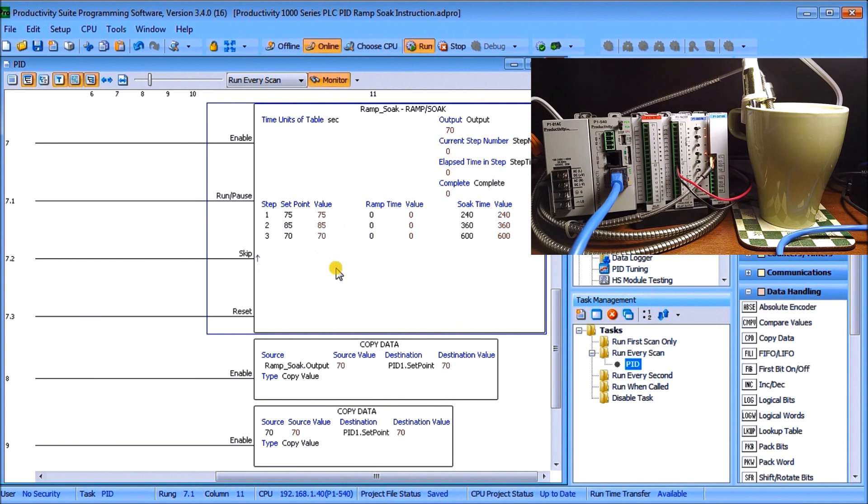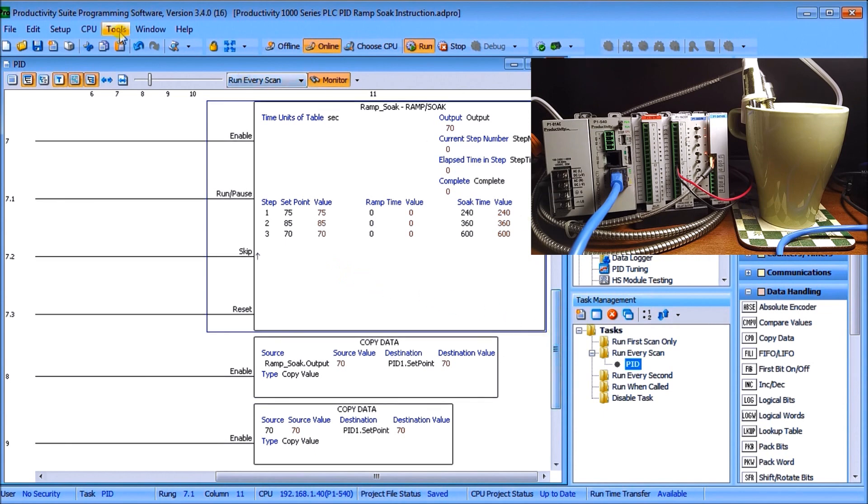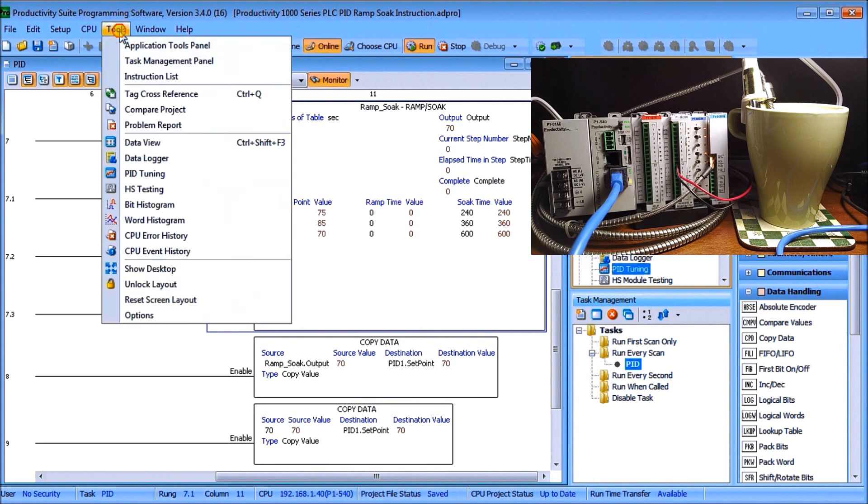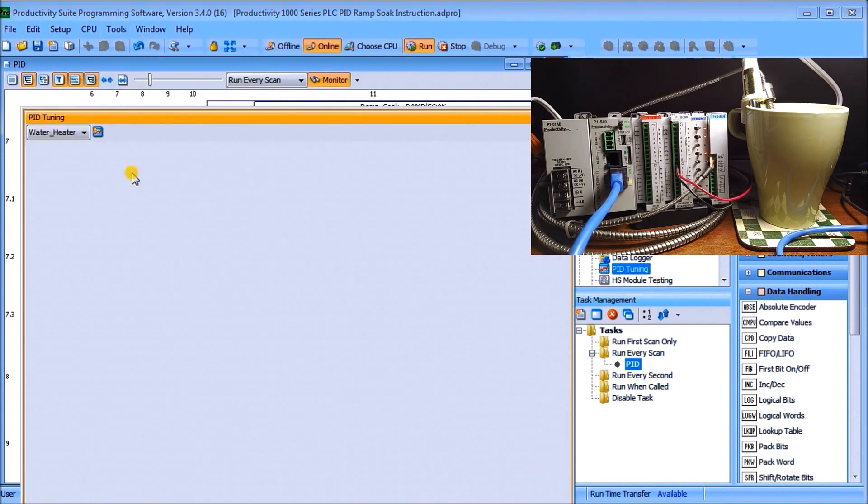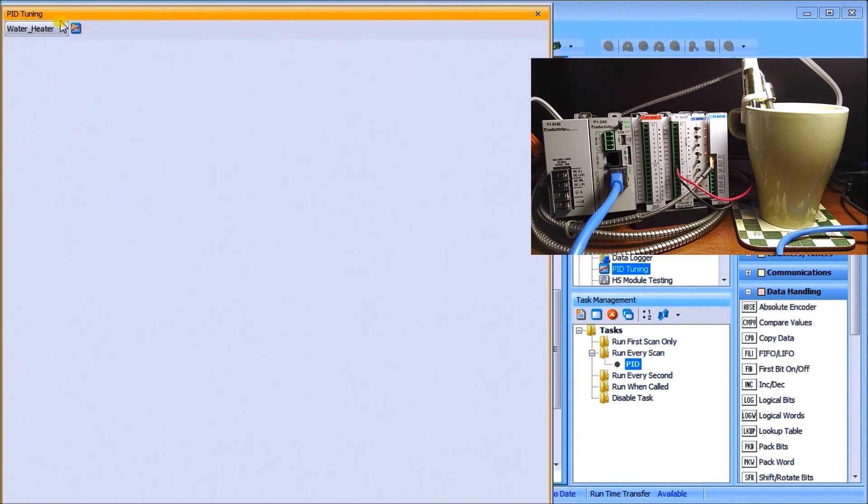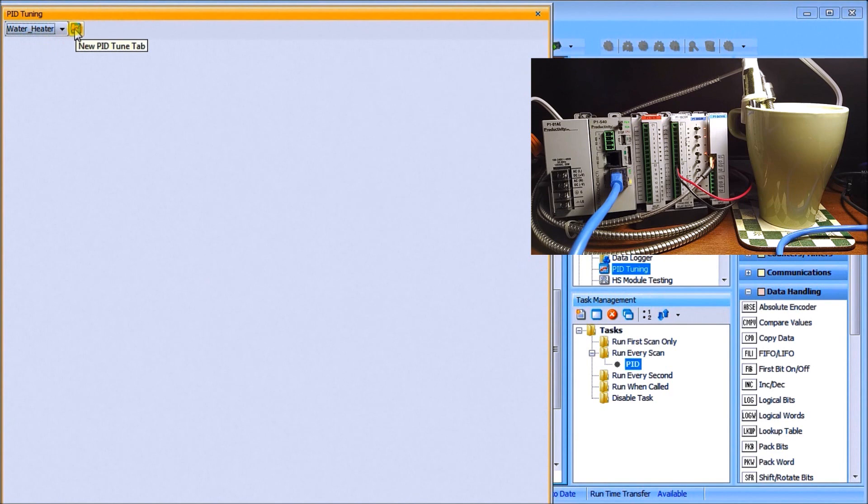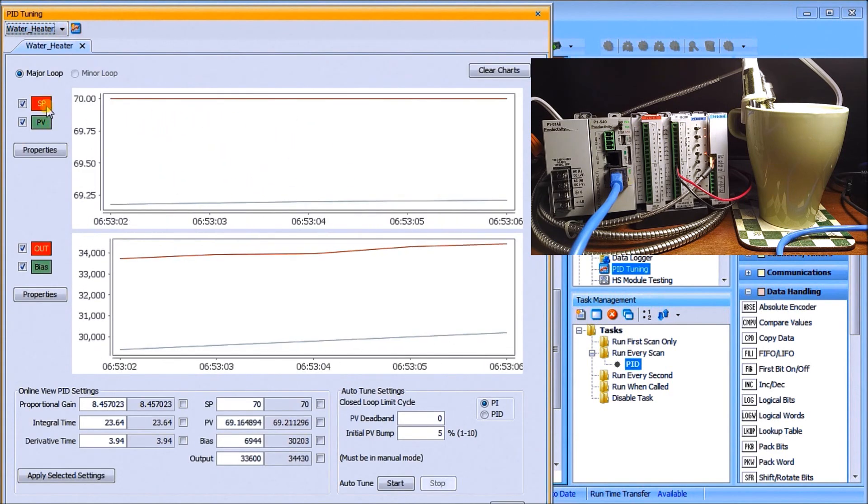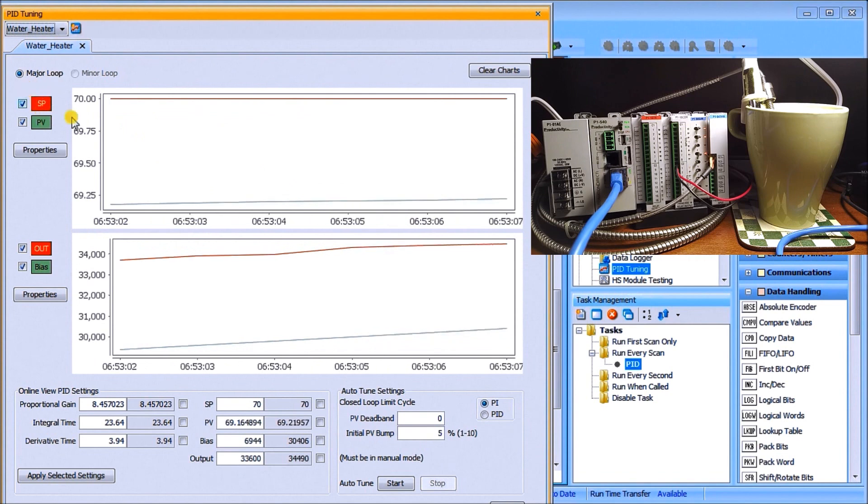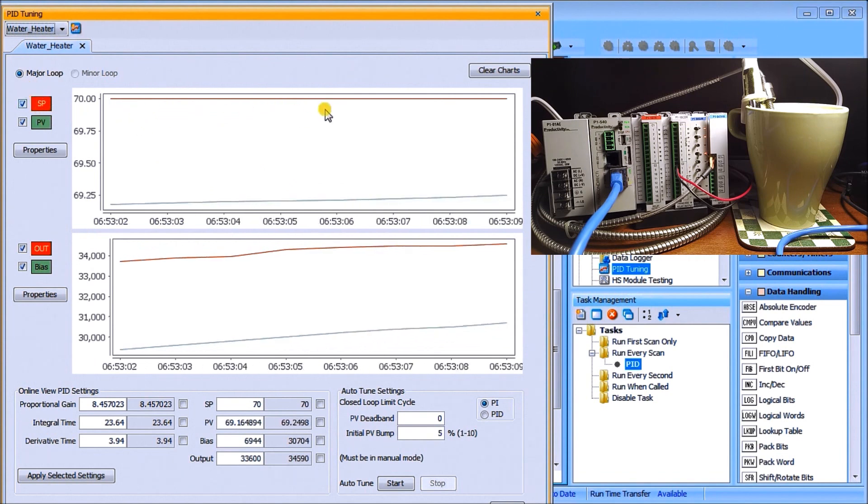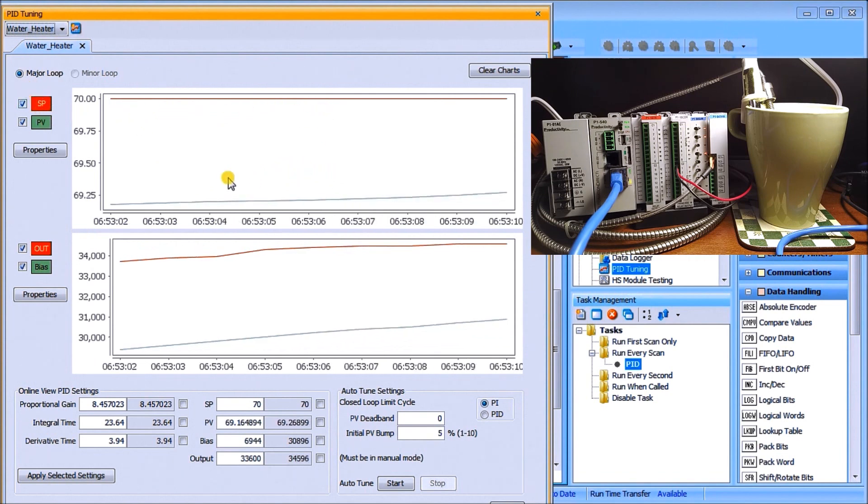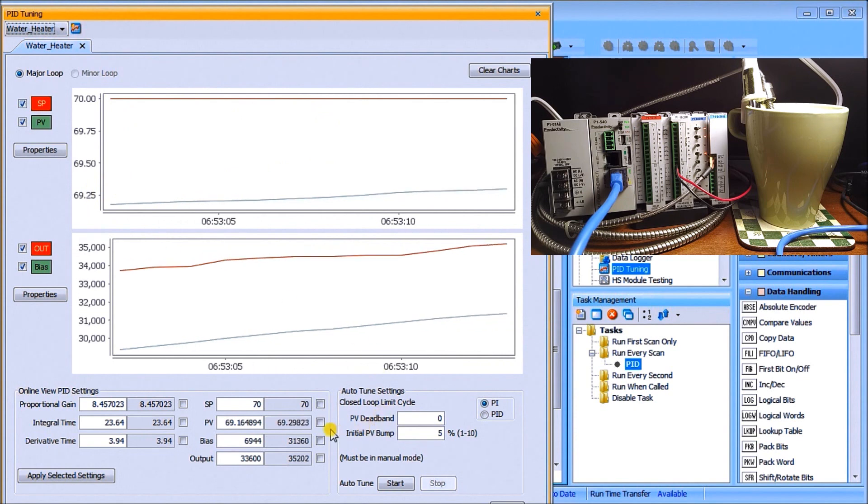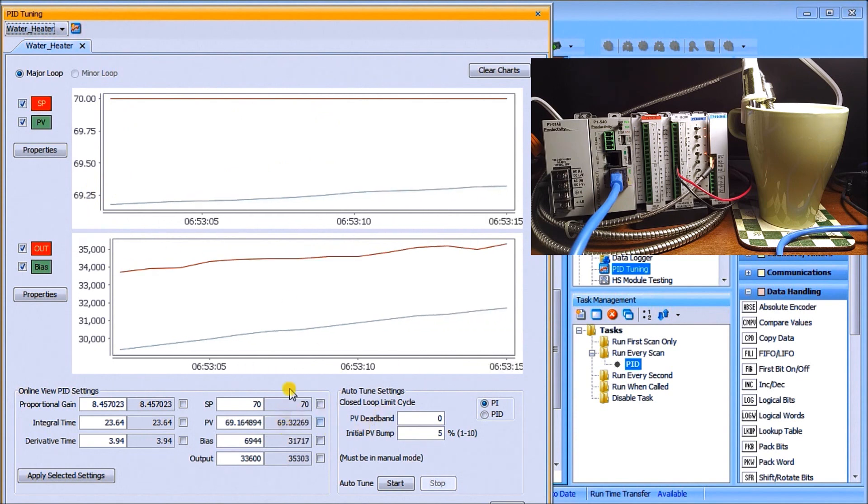So we have everything set up, what we'll do is we will call up our PID tuning. It's located under the application tools under monitoring and debug, it's called PID tuning, or we can go under tools and then call up PID tuning. When we do we'll select our water heater and we will look at that process variable and set point so now we see it's 70 and our process variable at 69.3 right now.